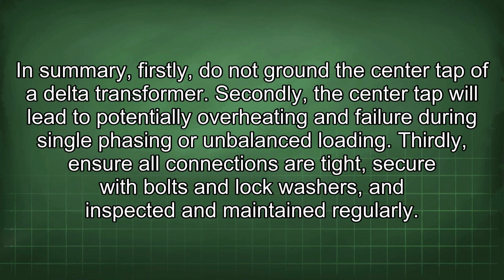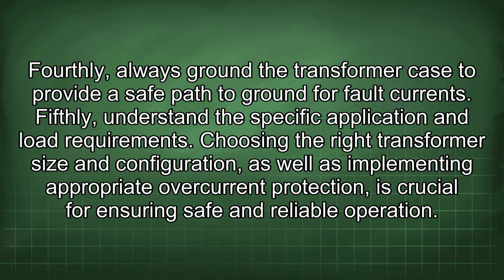In summary, firstly, do not ground the center tap of a delta transformer. Secondly, grounding the center tap can lead to potential overheating and failure during single phasing or unbalanced loading. Thirdly, ensure all connections are tight, secured with bolts and lock washers, and inspected and maintained regularly. Fourthly, always ground the transformer case to provide a safe path to ground for fault currents. Fifthly, understand the specific application and load requirements. Choosing the right transformer size and configuration, as well as implementing appropriate overcurrent protection, is crucial for ensuring safe and reliable operation.